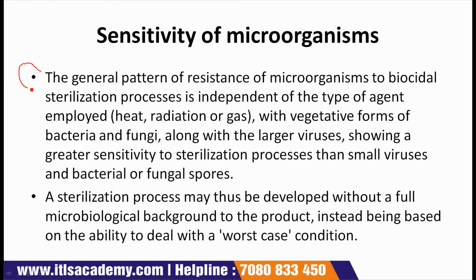First point is the general pattern of resistance of microorganisms to biocidal sterilization processes is independent of the type of agent employed, and these agents are heat, radiation or gases. The sterilization process will be independent of these heat, radiation or gas.